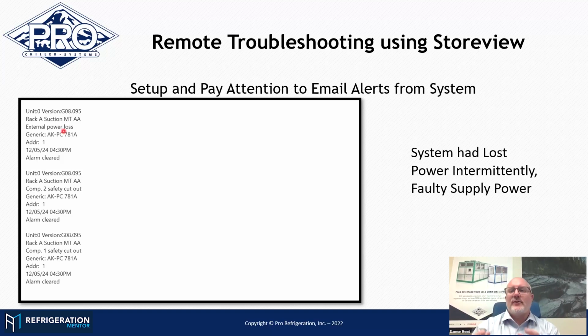Well, inside of the control circuit of the systems, we have a battery backup UPS for all of the low voltage controls. So if there's a power failure, that UPS says, hey, I lost power, I'm going into an alarm mode. Boom, that triggers an alert. Then your compressors, so you imagine you lose line power, now your compressors go to do something and they're like, hey, I ain't got the right power. Boom, I get safety cutouts at the same time.